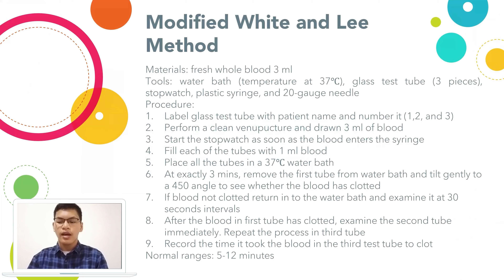Normal range result from this method is 5 until 12 minutes, and then there is some advantage and disadvantage from this method. Advantage: more accurate and standard method. Test can be run without control, and the disadvantage is the temperature should be maintained because higher temperature accelerates clotting, and the diameter of the glass tube should be uniform.